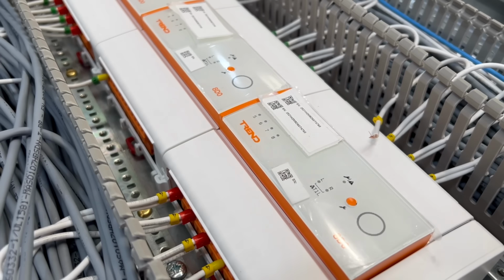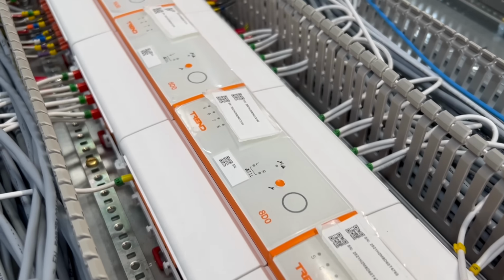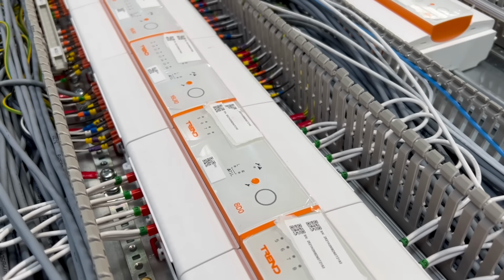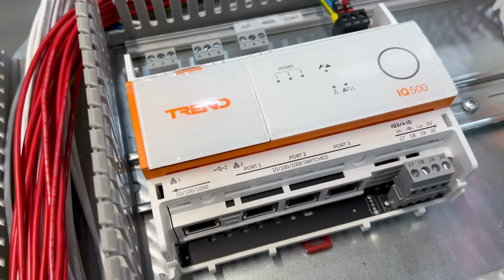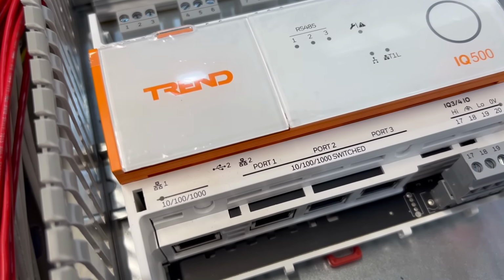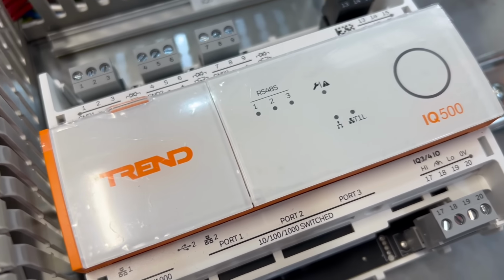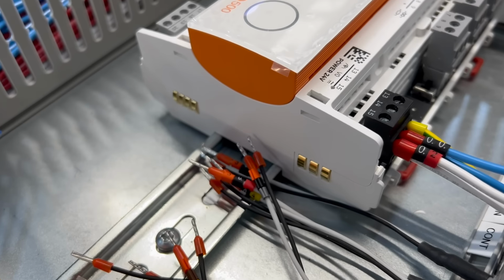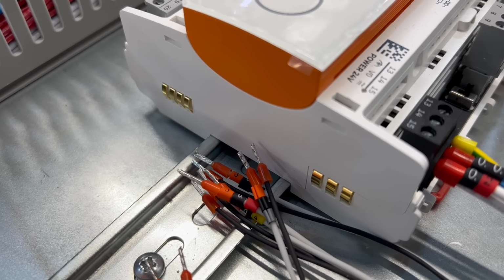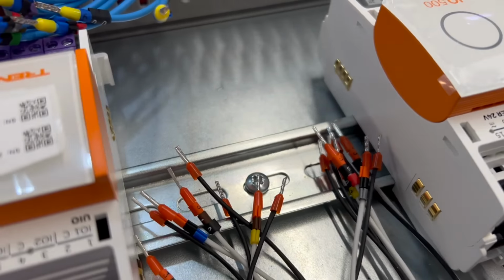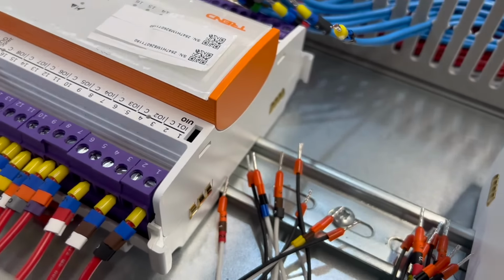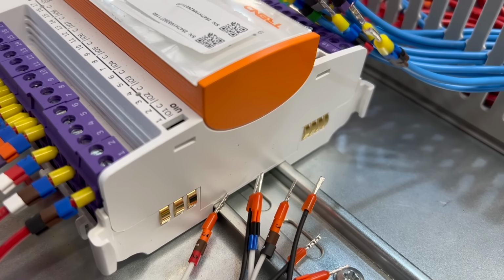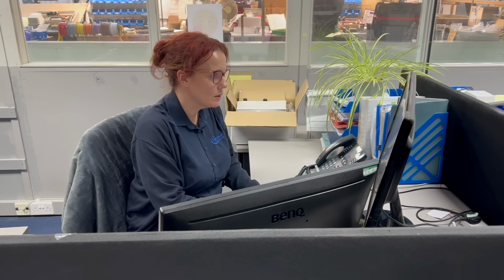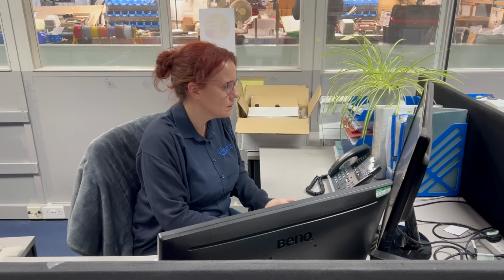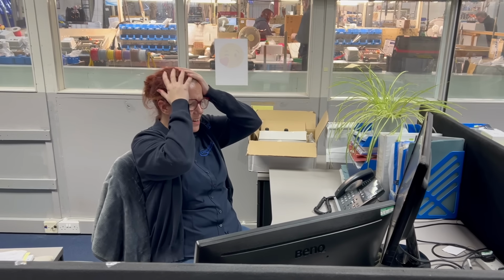You'll also notice that the IQ5 has a modular design. Some DDCs will have a number of input and output connections built in, but depending on the model and the needs of the installation, you can expand the number of inputs and outputs by adding extra modules to the controller. These simply clip onto the DIN rail and connect via a comms ribbon or bus connector. It means the system can grow as the building's needs change, which is handy when an architect decides halfway through the job that the small office extension actually needs an entire new ventilation plant. Happens more often than you'd think.